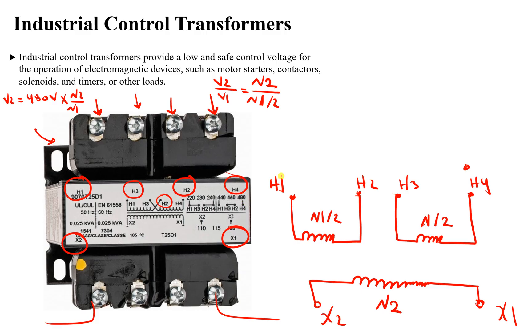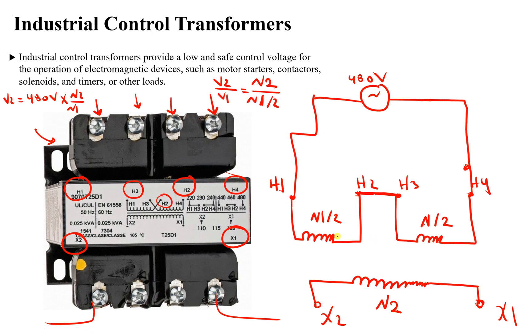Now what if I have an input of 480 volts? For this case, connect H3 to H2 — these two terminals are connected together. Then connect the first terminal of the supply to H1 and the second terminal to H4. You will see that these two coils are now in series, so the total voltage is 480 volts and the total number of turns is N1.